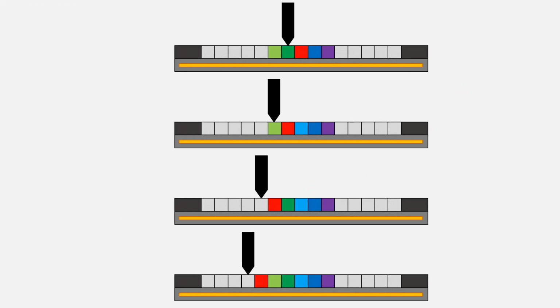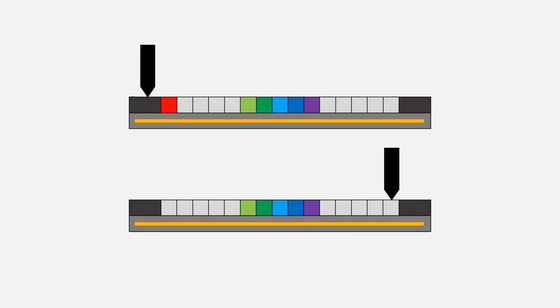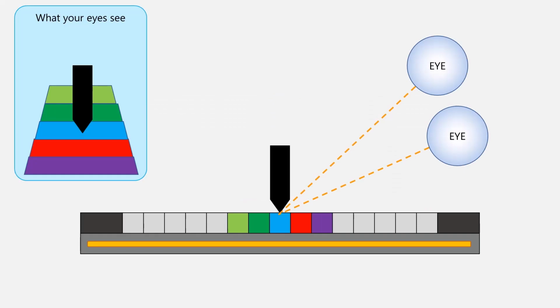Here is a simple example of a visual disagreement. The tip of the pen is pointing at 1 pixel, but the tablet thinks the pen is pointing slightly to the right. So there is a little bit of displacement between the tip of the pen and the pointer, and that displacement will persist even as the pen moves. The displacement creates some odd situations at the edges of the display. Sometimes the pen is not pointing at a pixel, but the tablet thinks it is. And sometimes the pen is pointing at a pixel, but the tablet thinks it is not pointing to a pixel. This is a very, very simple example of a real inaccuracy, and you can see it in the cross-section. And because there is no parallax, your eyes will consistently and correctly see the inaccuracy.